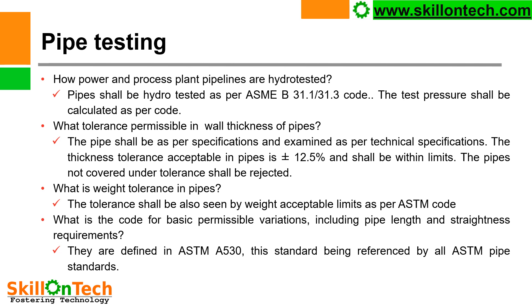What tolerance is permissible in the wall thickness of a pipe? The pipe shall be as per specifications and examined as per technical specifications. The thickness tolerance acceptable in pipe is ±12.5%, and shall be within limits. Pipes not covered under these tolerances shall be rejected.